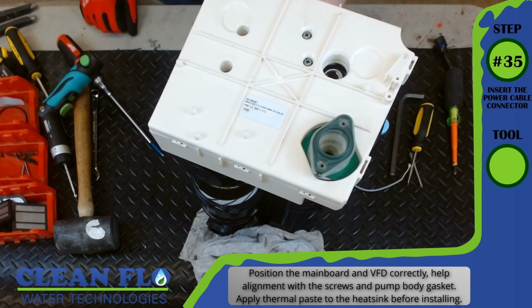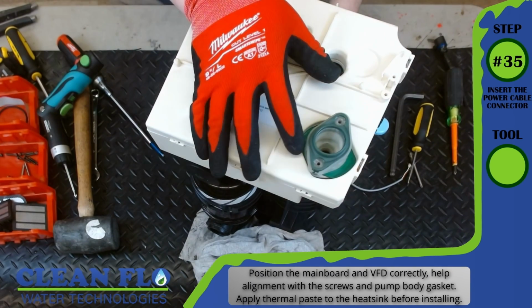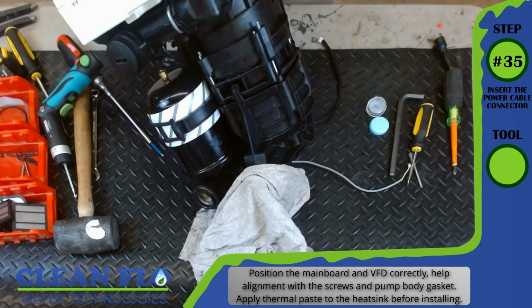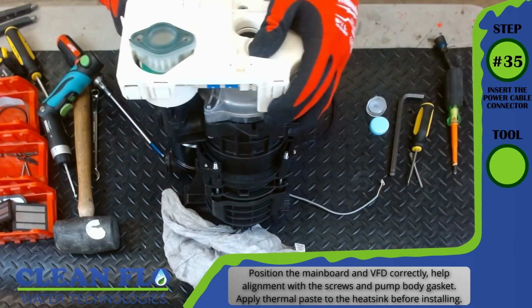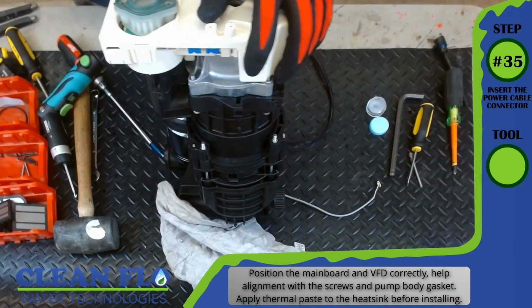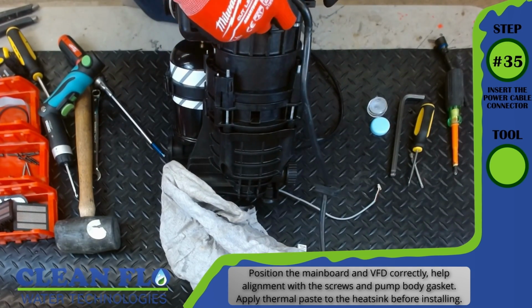Step number 35, insert the power cable connector. No tool required. Position the main board and VFD correctly. Help alignment with the screws and pump body's gasket. Apply thermal paste to the heatsink before installing.